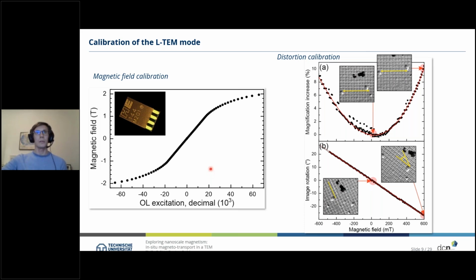But if we change the main lens of the electron microscope, of course we will have a strong impact on the beam itself, on the image, on the magnification, and so on. So we also need to take care of that, and that is shown here on the right-hand side, where we start by looking at the image rotation as a function of the magnetic field. When we apply a magnetic field, as we expect, we have an image rotation which is linear with the applied magnetic field. So that is quite easy to compensate afterwards in the post-processing of our experiment.